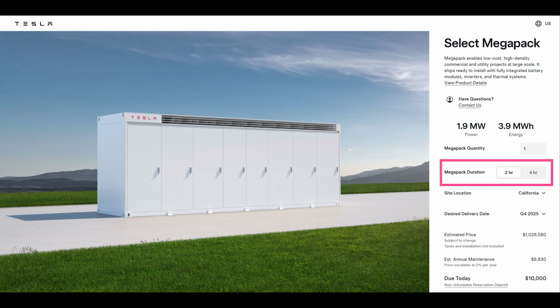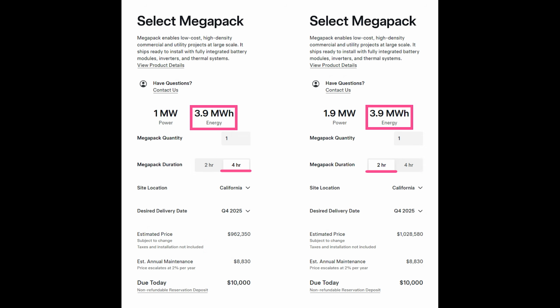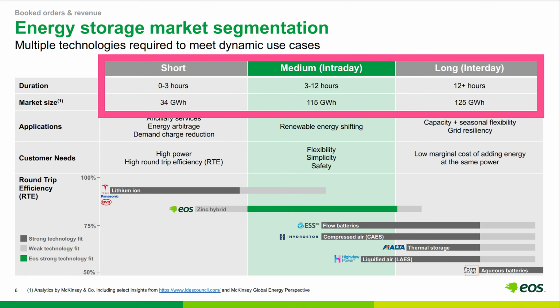For example, Tesla offers 2 duration options for their megapacks, 2 and 4 hour. Each has about 4 megawatt hours of energy capacity, but the 2-hour version has roughly 2 megawatts of inverter power, and the 4-hour version has 1 megawatt of inverter power. Because duration is based on the maximum discharge rate, there's nothing stopping a customer from discharging a megapack more slowly to provide 12 hours of duration. It just likely wouldn't be cost competitive.